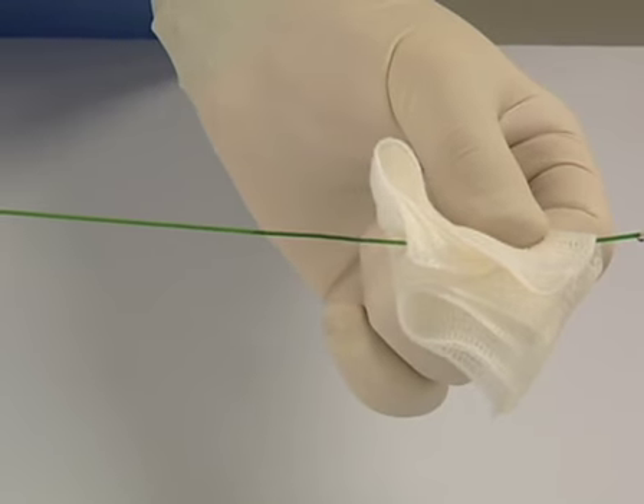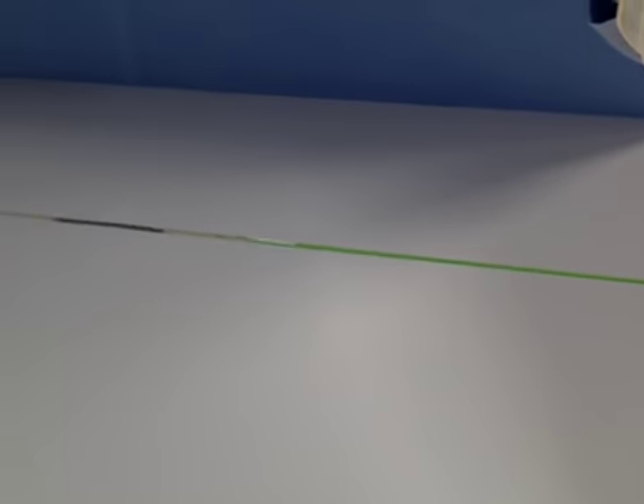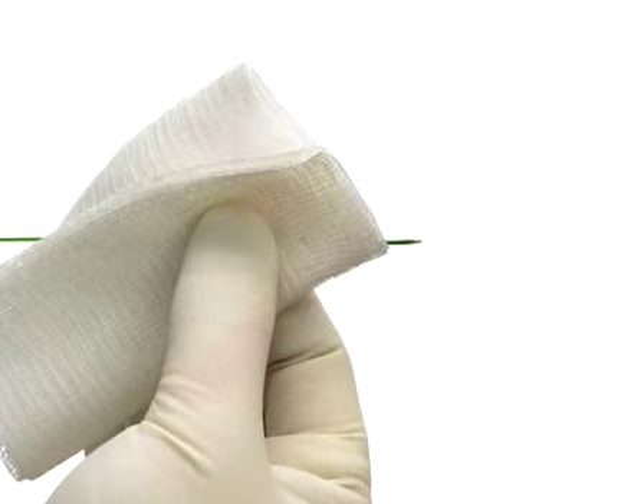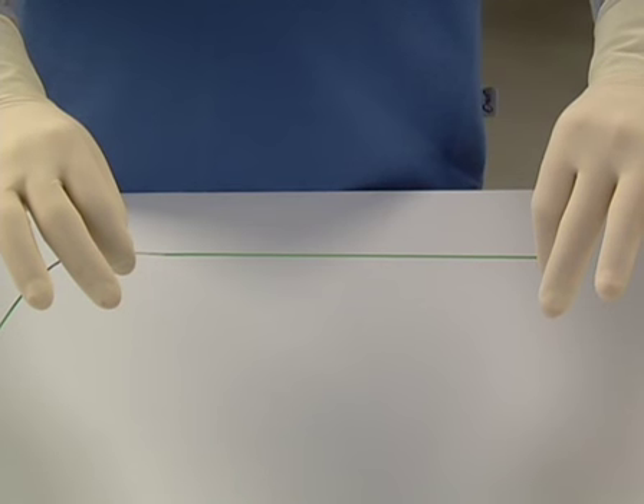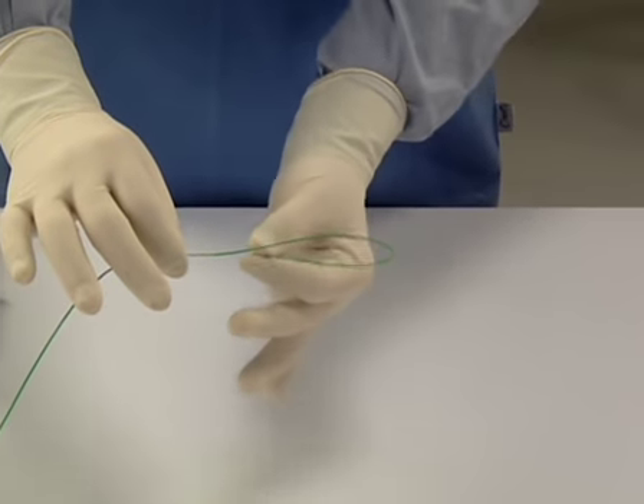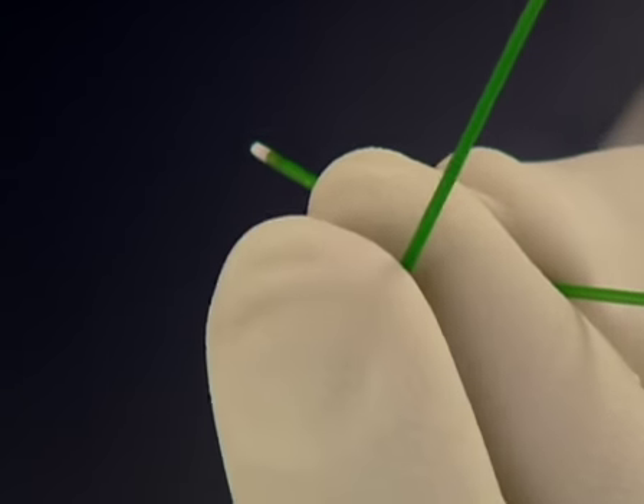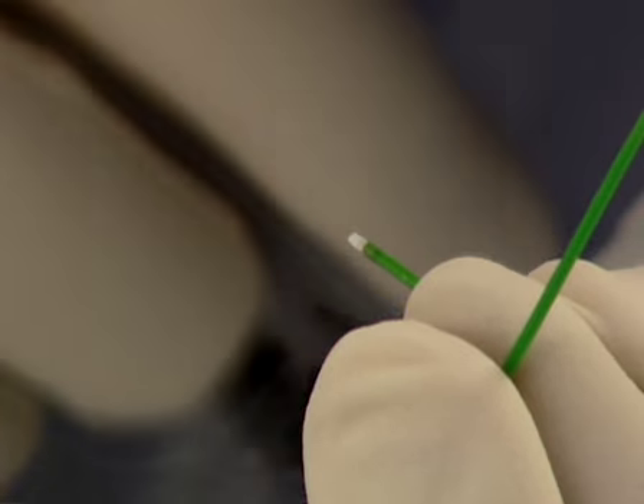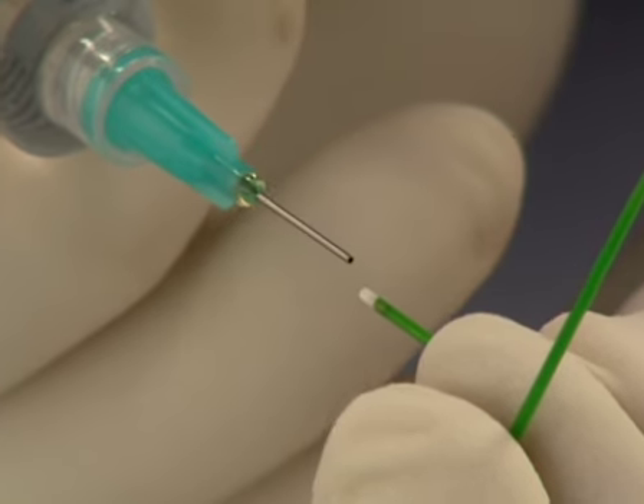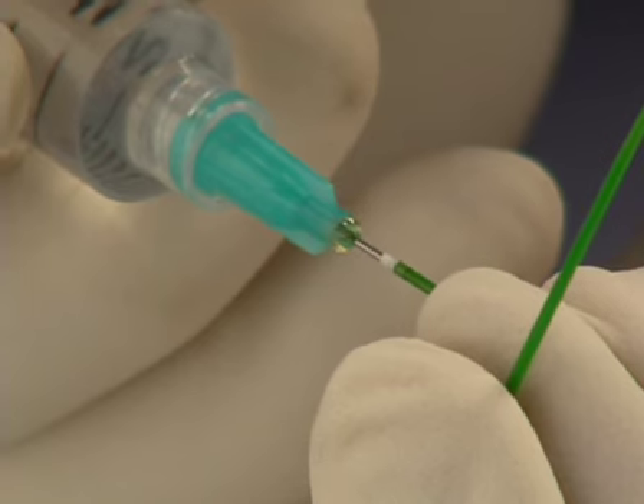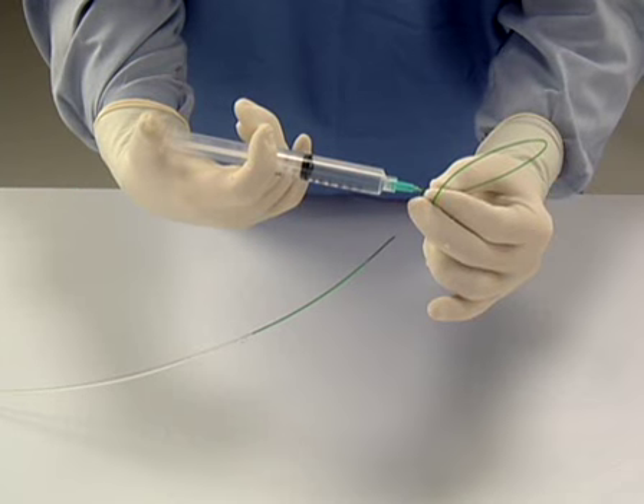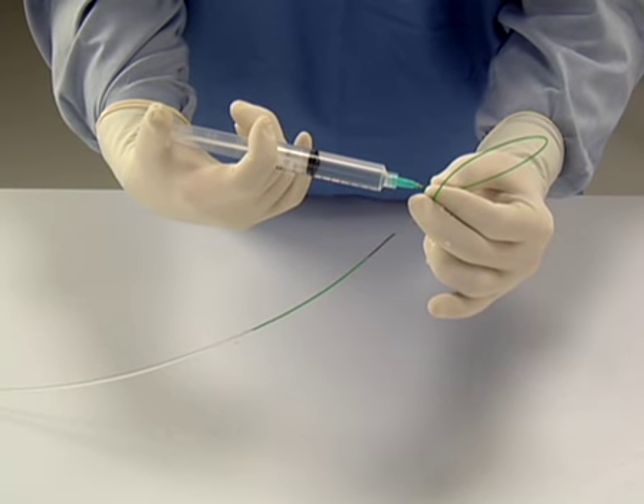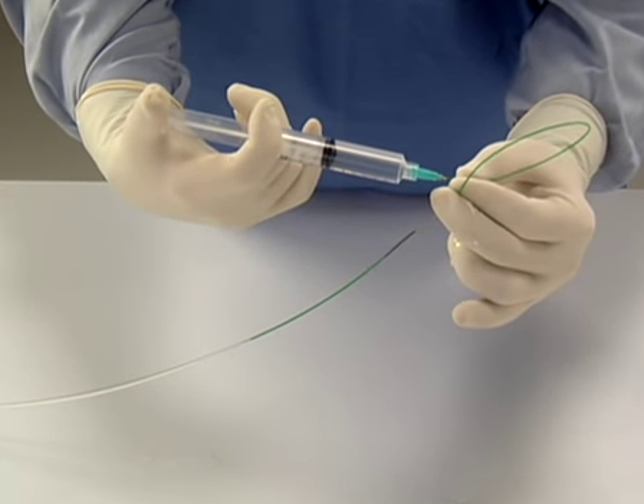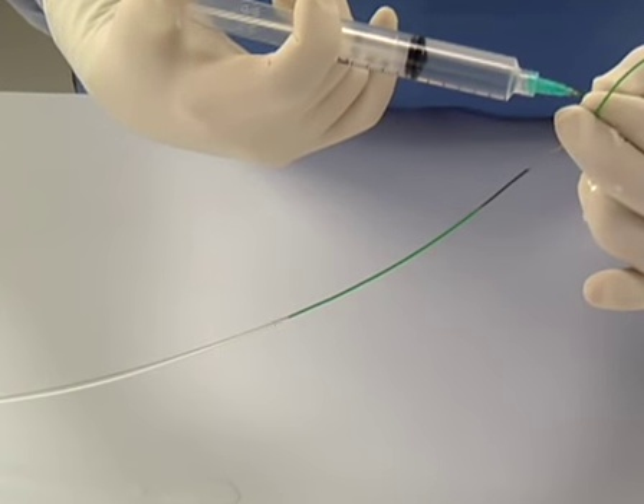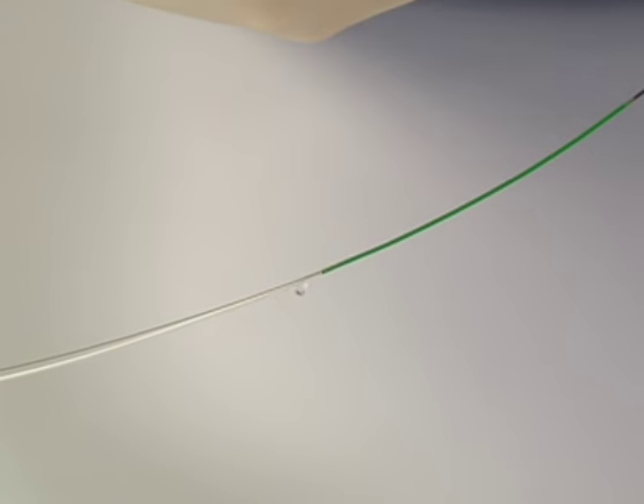Gently pull the filter completely into the clear segment until it reaches the automatic stop. Do not grip the white distal tip directly. To ensure proper flushing, gently press a finger against the primary wire port to block it. Using a syringe and the prepackaged blunt end needle, flush the distal tip of the delivery end with sterile heparinized saline. Flush until fluid passes out the capture wire exit port and all air is removed from the catheter.